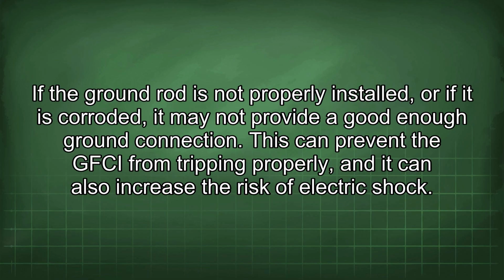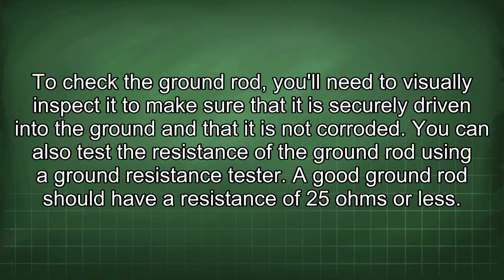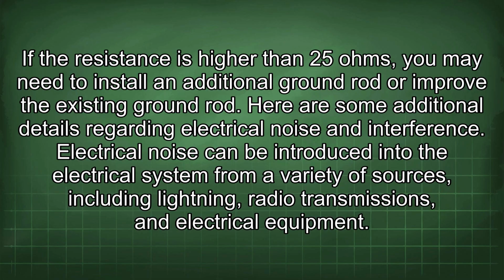wire. If the ground rod is not properly installed, or if it is corroded, it may not provide a good enough ground connection. This can prevent the GFCI from tripping properly, and it can also increase the risk of electric shock. To check the ground rod, you'll need to visually inspect it to make sure that it is securely driven into the ground and that it is not corroded. You can also test the resistance of the ground rod using a ground resistance tester. A good ground rod should have a resistance of 25 ohms or less.